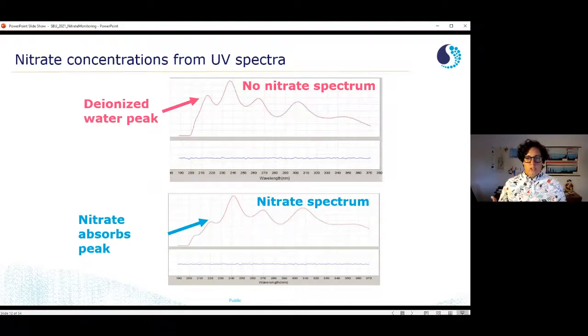So we have two spectrums here. One on the top is that we just have deionized water. We have no nitrate in that water, and you can see what the spectrum looks like. If we actually spike that water now with nitrate, you can see that that peak in that range that we just talked about in the blue box tends to go down. And whether that peak gets bigger or smaller, that's actually how the instrument is measuring how much nitrate is in the water. And this is actually done with like a linear regression kind of method. Okay.